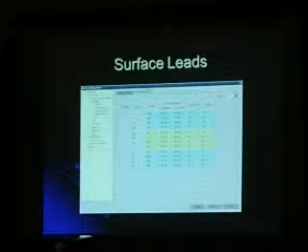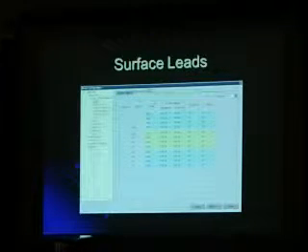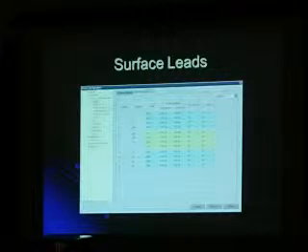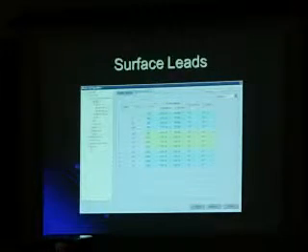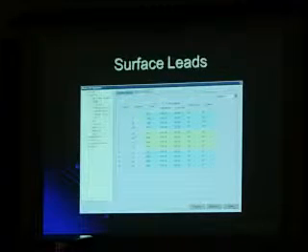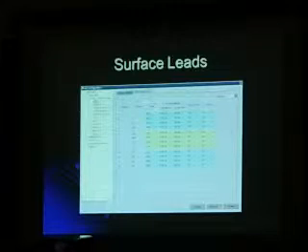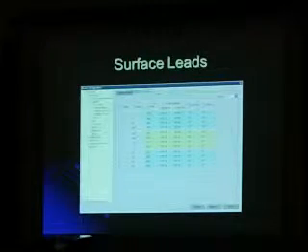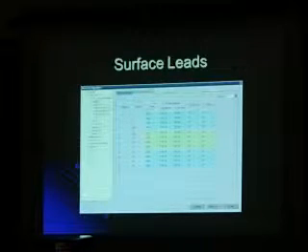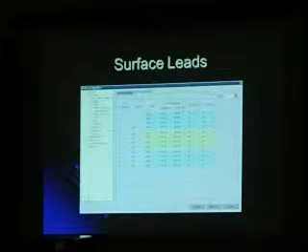Now one of the tricks that I use to see how clean my lab is on leads 1, 2, and 3, because they're the most stable of them, and you might as well at least give it half a chance, is I'll turn the notch filter off and see how much noise is in the room. In 90% of the labs, the moment I turn that off, their signals go like this, because they're just not built very well. I turn the notch filter off so I can see how ugly the room is.